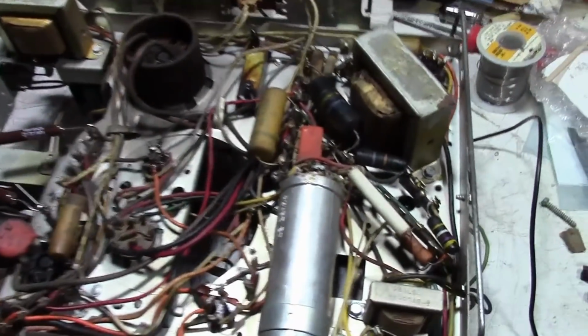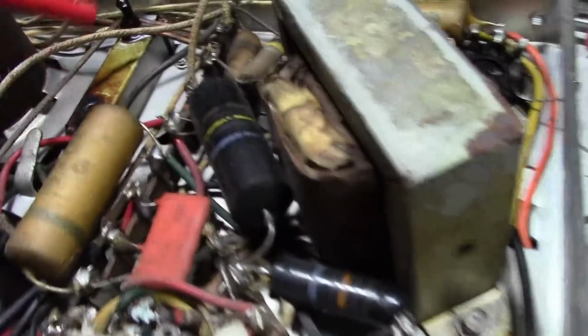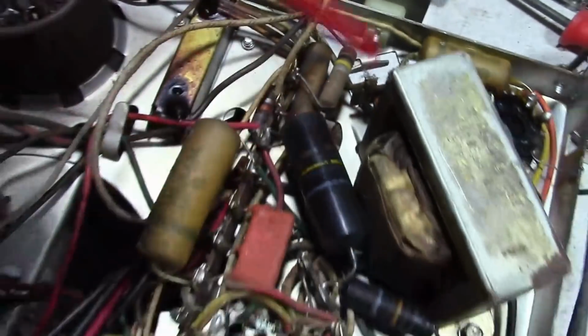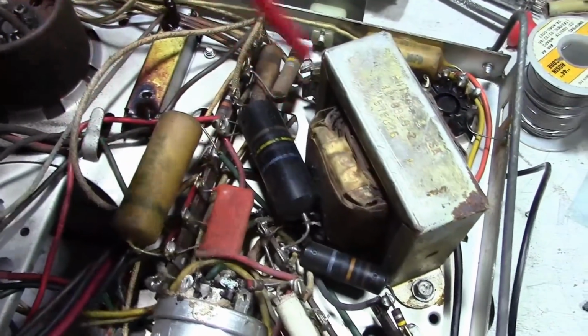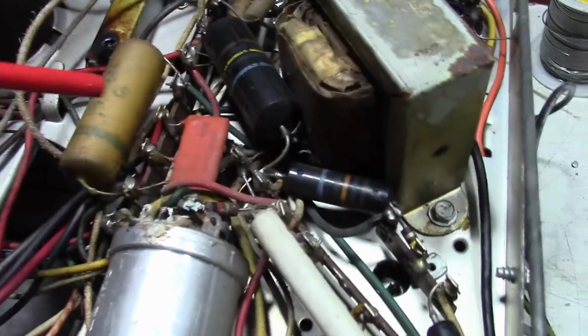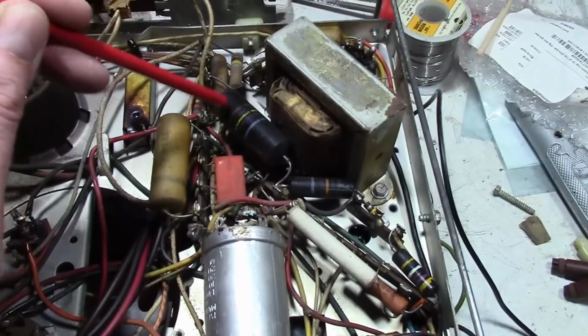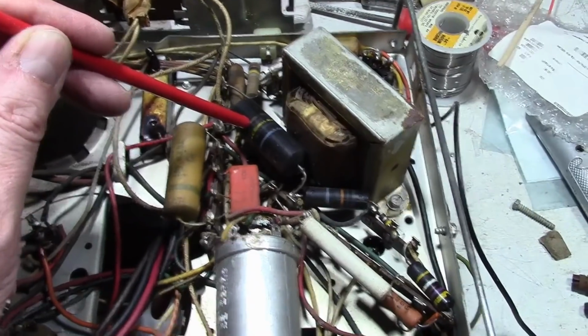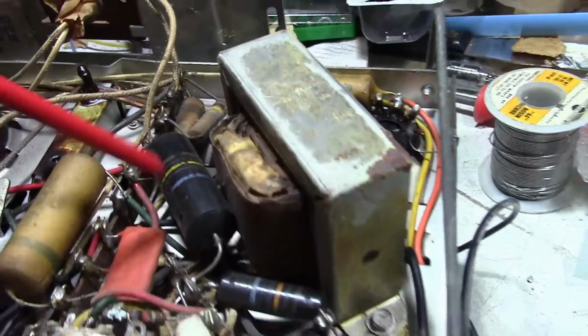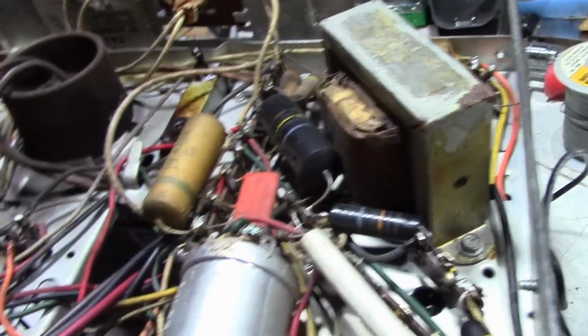As near as I can tell from just doing a visual inspection, this looks a little charred down in here, and the smoke seemed to be coming from this area. I also know from experience that this cap right here is directly across the AC line. I don't see it cracking on either end, but these are notorious for going bad.